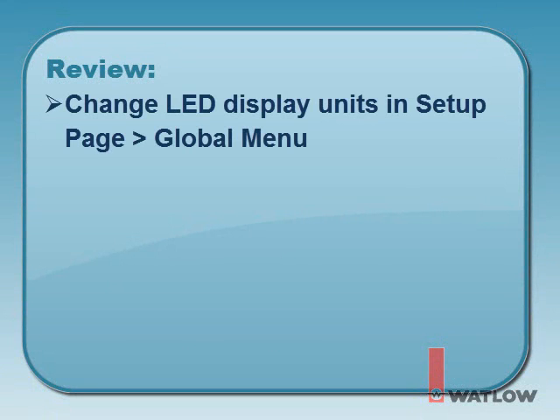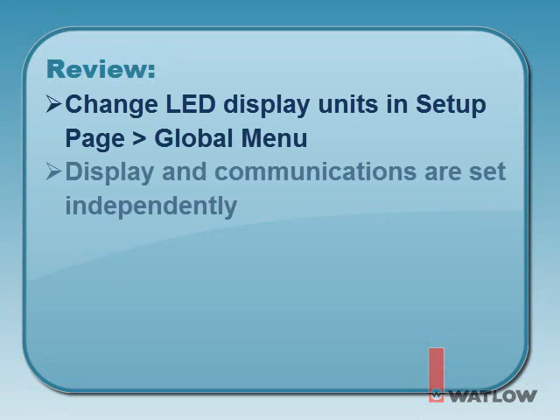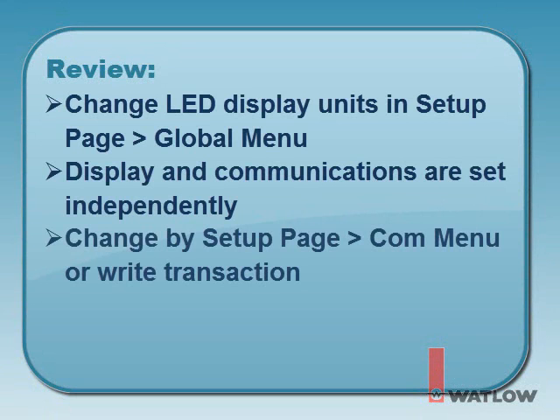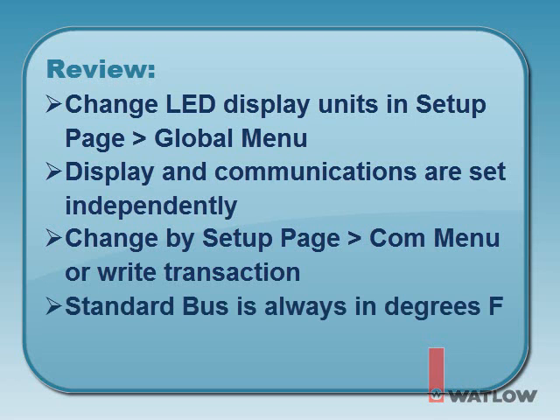Let's review what we've covered. We've demonstrated how to change the display units of the seven-segment display in the setup page global menu. We discussed that the communications data is independently set and to make the change by either entering the setup page communications menu or performing a write transaction using the communications protocol, and that standard bus always sends all temperature-related data in degrees Fahrenheit via the EIA 485 serial port.